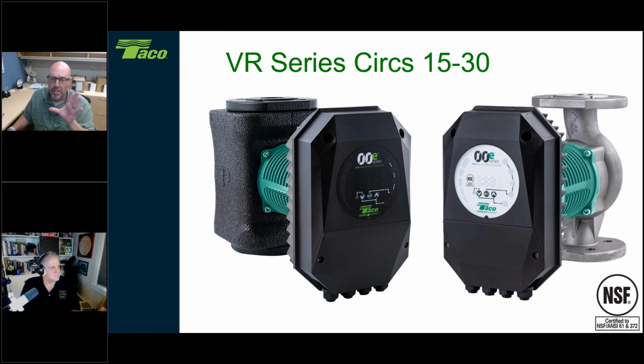So obviously, also the differences other than just the cast iron and stainless, you'll also see by the faceplate. The cast iron circulator would have a black faceplate, and a stainless steel will have a white faceplate, also with the NSF certification designation on the front side of it as well. So when these things get all insulated, they do come with this insulation jacket that you see as well. But once you insulate the whole project, then you don't know what's behind the insulation. At least you can tell just by looking at the faceplate whether it's going to be a stainless steel or a cast iron model.